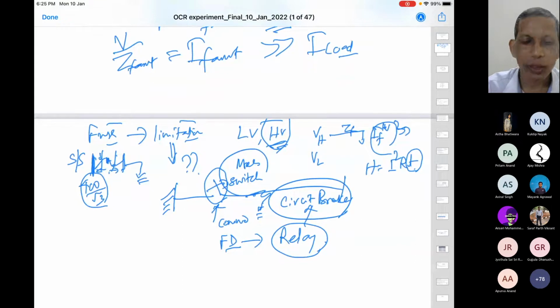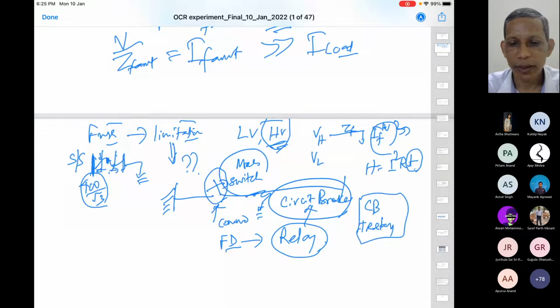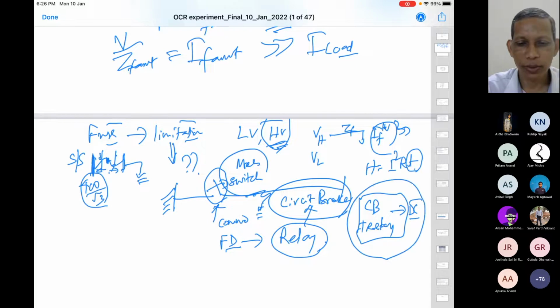So essentially a circuit breaker plus a relay are the essential elements in this business. The relay is a numerical device, and the circuit breaker has to be opened through an electromagnetic coil, through motorized action, which releases the tightened mechanism. So we require a DC supply for both. A battery supply, which we call the station battery arrangement, is essential. These are the three basic elements of a protection system in a high voltage system.